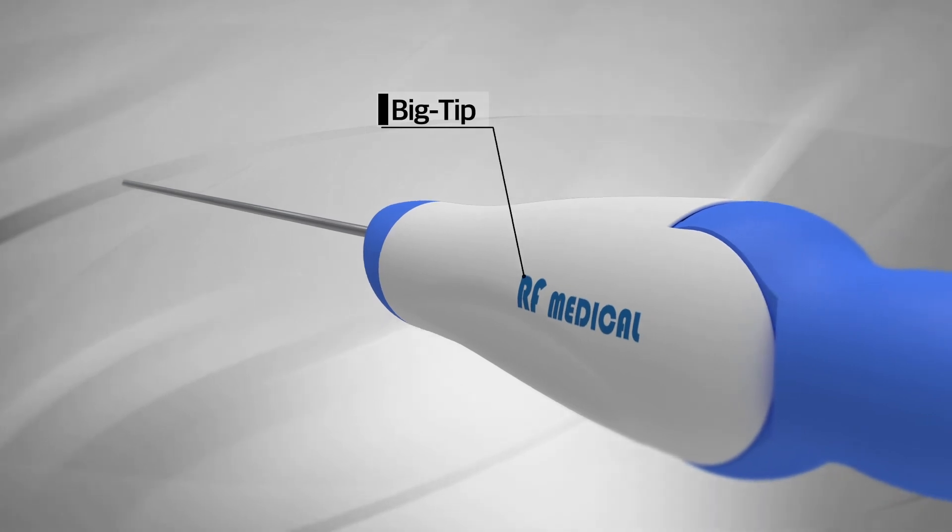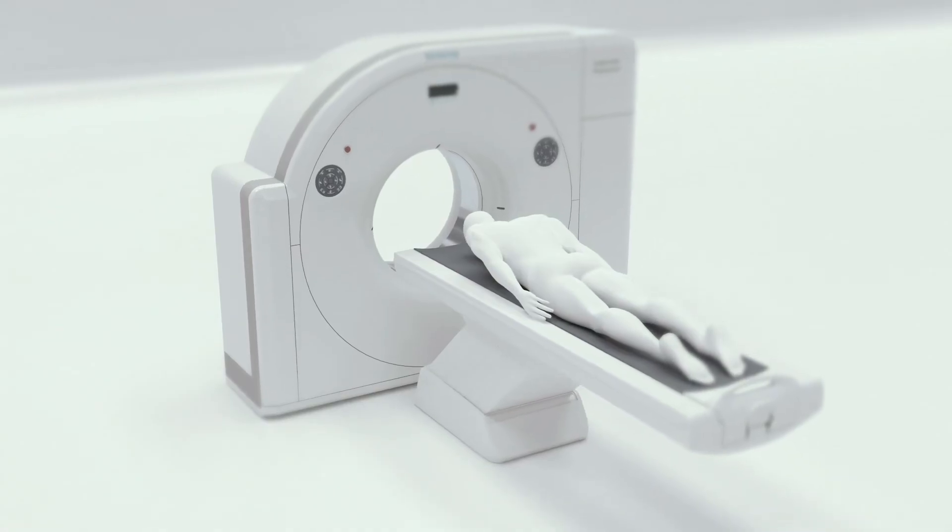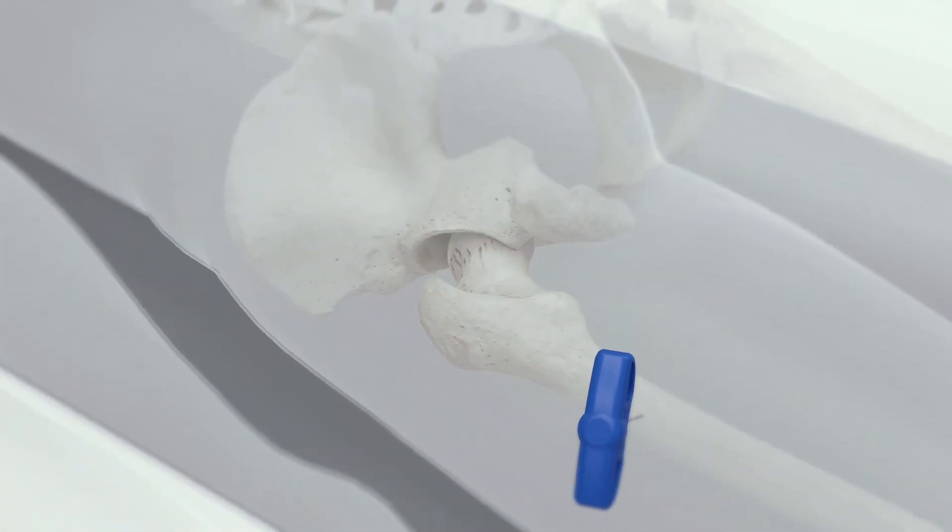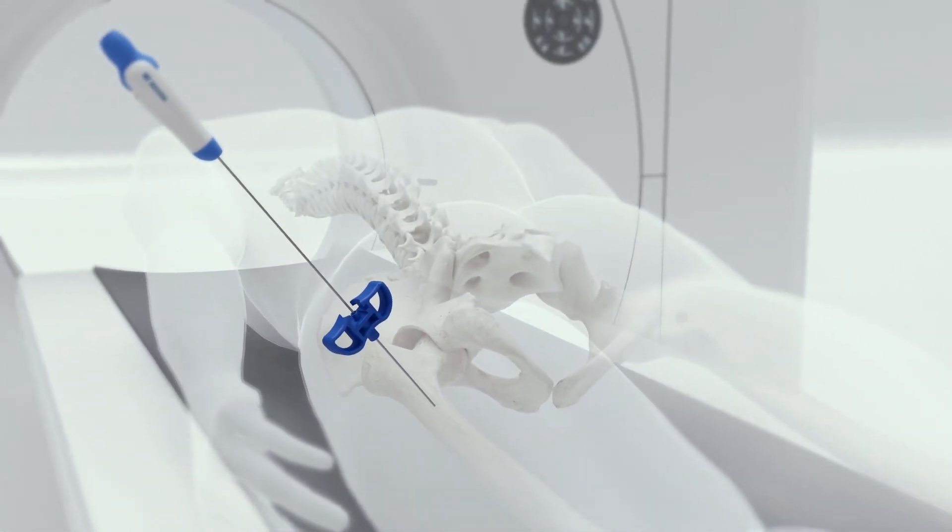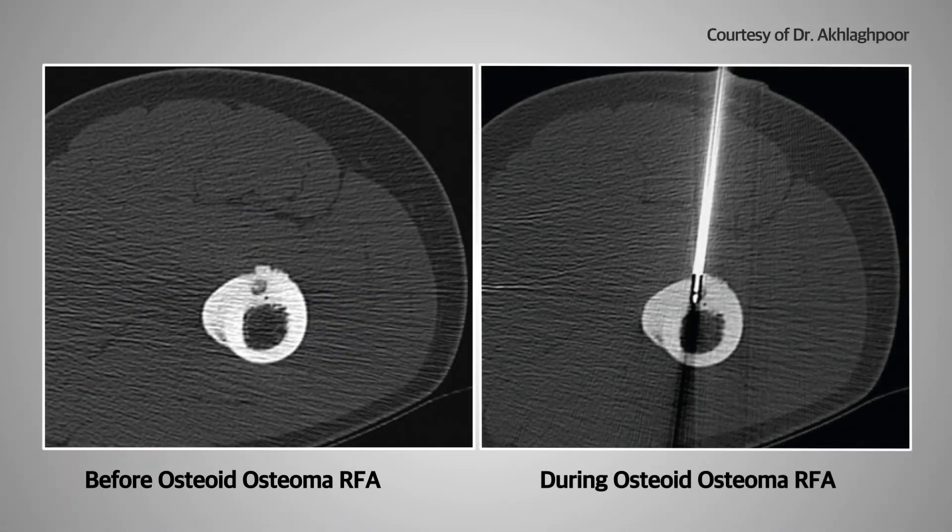Radiofrequency ablation of osteoid osteomas can be done with the Big Tip electrode and VCT electrode. For the radiofrequency ablation of osteoid osteomas, a practitioner needs to ablate only the nidus of the osteoid osteoma, which is why the Big Tip and VCT electrodes with short active tip length are sufficient to obtain spherical and predictable ablation areas.